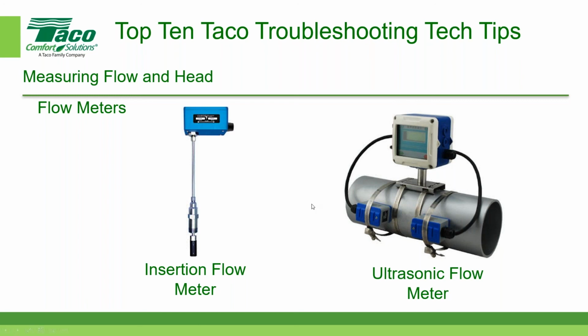Are you quietly suggesting you need to read the instruction sheets of the flow meter? Well, when you deal with this on a daily basis, you get all kinds of things. And I would have to say that the overwhelming majority of data that we get from the field is pretty good. People know what to do, they know how to do it and so on. But if we get wacky readings, then we start digging, and that's when you wind up with these crazy things where you wind up with an elbow at the inlet and a valve at the outlet. And yeah, you're right, Brett. When all else fails, read the owner's manual.